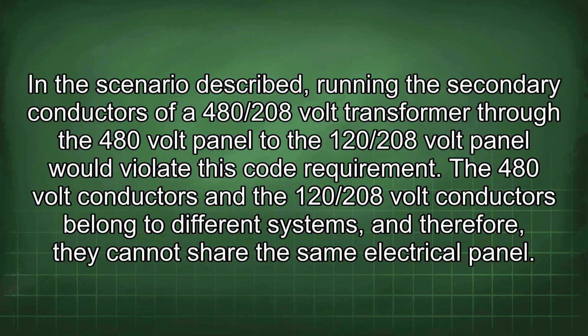In this scenario described, running the secondary conductors of a 480/208 volt transformer through the 480 volt panel to the 120/208 volt panel would violate this code requirement. The 480 volt conductors and the 120/208 volt conductors belong to different systems, and therefore they cannot share the same electrical panel.